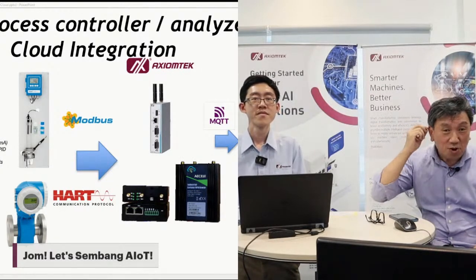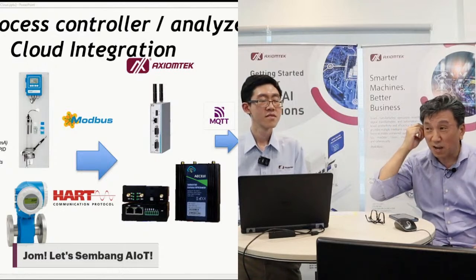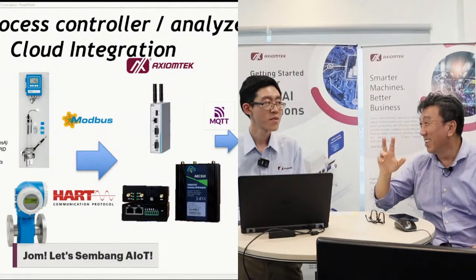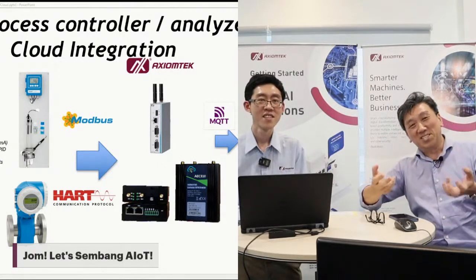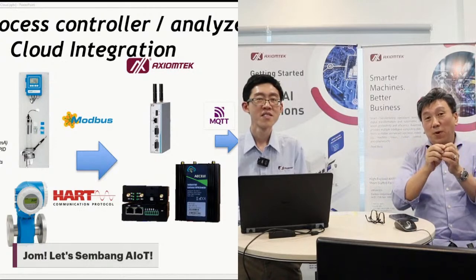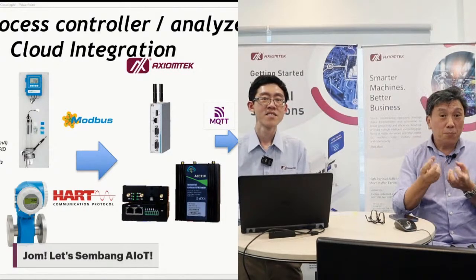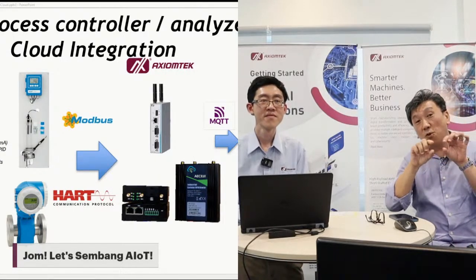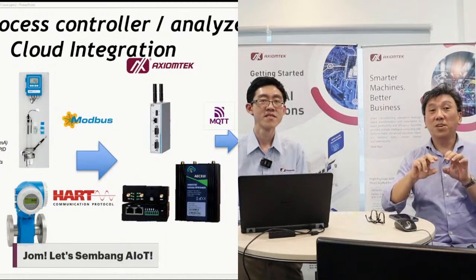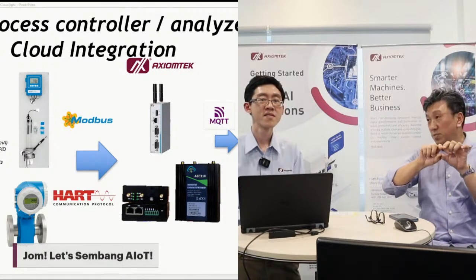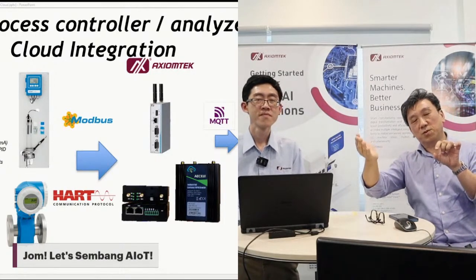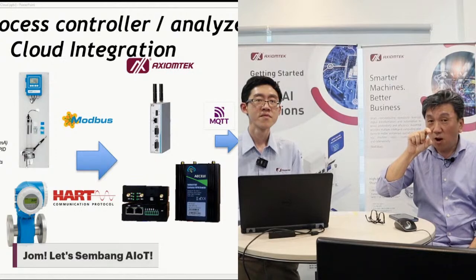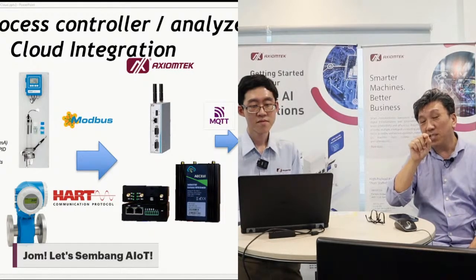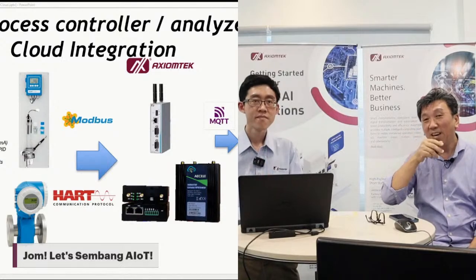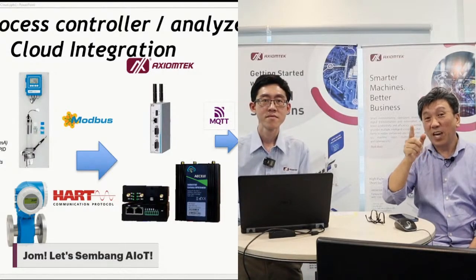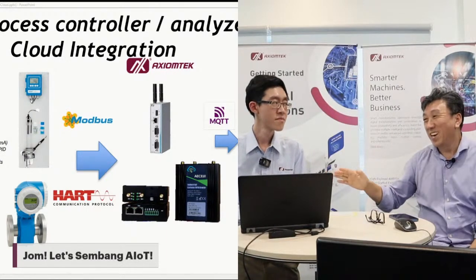So it's running between 1000 hertz to 2000 plus hertz. So if you put it to your ear, if you transfer it to sound, it sounds something like that. So it's kind of digital within the analog. By using that, it's able to superimpose this set of signal onto the 4 to 20 milliamp bus. So that equipment already giving you a 4 to 20 milliamp bus on a DC, 4 to 20 is basically a DC within 10 to 30 volt DC. So on top of this bus, it will transmit this FSK signal on the 1.2K baud, 1200 bits per second, very slow, not highway, it's very slow.